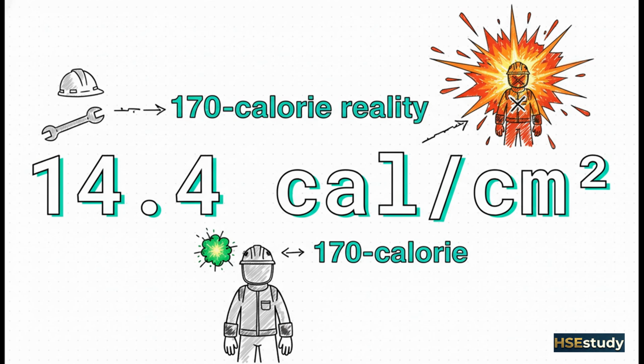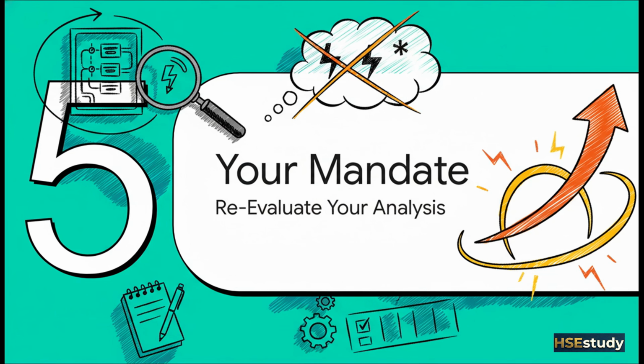So your electrician suits up in 20-cal gear thinking he's protected. He thinks he's safe, but he's not facing a 14-calorie hazard. He's facing a 170-calorie inferno. This right here, this is how fatalities happen. So this brings us to your mandate. Your responsibility as a safety professional, as an engineer, as a site leader. You have to go back and you have to critically reevaluate your arc flash hazard analysis, and you have to hunt for this specific dangerous assumption.